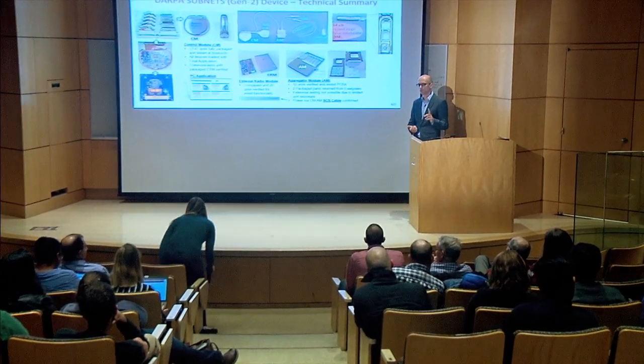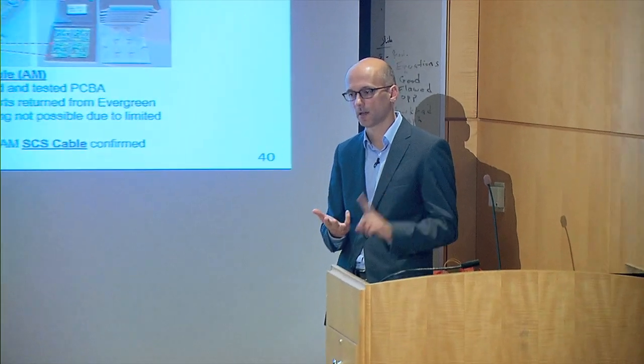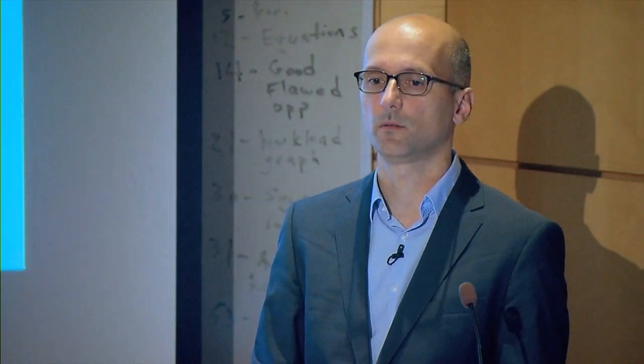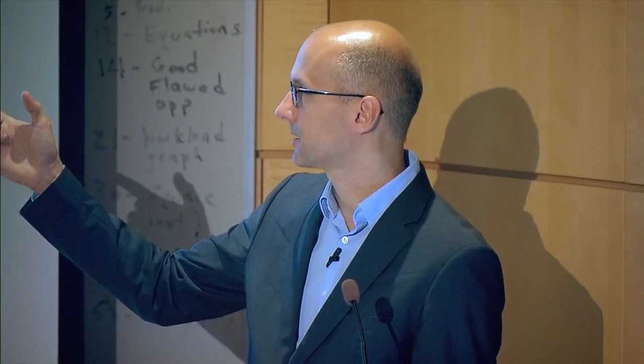So if you look into the numbers you need for biocompatibility, sterility, and first in human use, you really work through the numbers of what's necessary based on the volume of these devices. You needed to have a certain surface area, and that translates to a certain number of devices that you needed to do for biocomp sterility, packaging, and also human feasibility study builds that needed to be fully functional. So you come up to the numbers that add up to 40 units. Out of those, we plan to have 6 systems for clinical. So basically 6 chest modules, 6 AMs, 24 NMs, and the rest was just biocomp sterility.